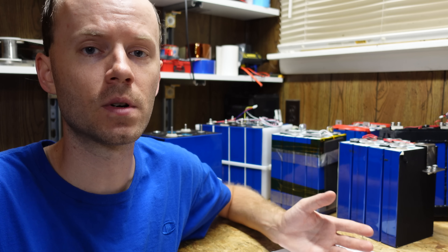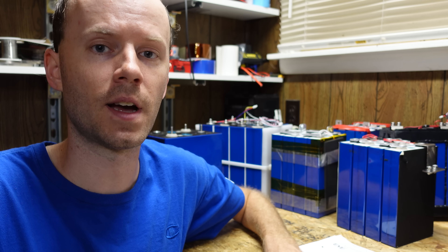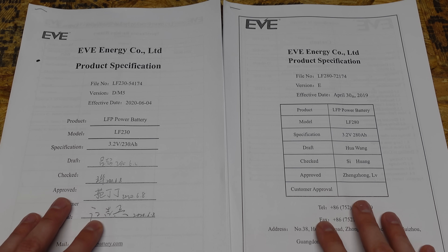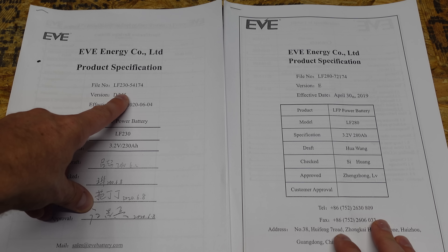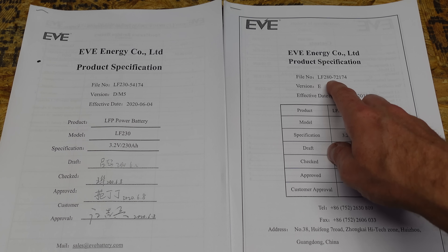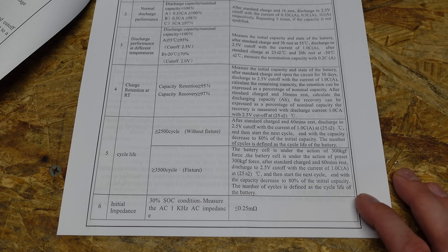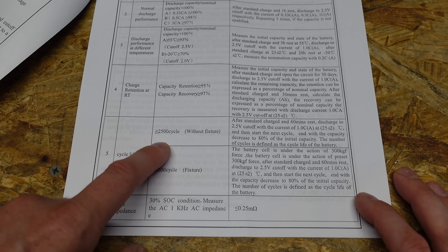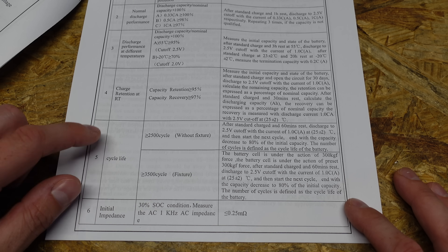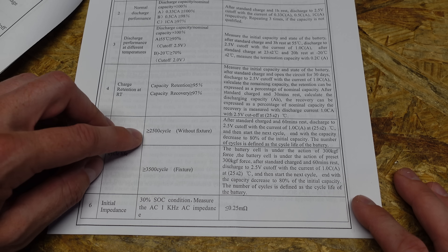We really need to establish whether or not the batteries actually need to be fixed, and to do that we're going to turn to the manufacturer's actual specification for these batteries. I have here the datasheet for the two cells I've been working with: the EVE LF230 version D specification, and the EVE LF280 version E specification. Starting with the 280, it gives a cycle life of 2,500 cycles without fixture and 3,500 cycles with fixture — so we're getting an additional 1,000 cycles if we fixture the batteries.